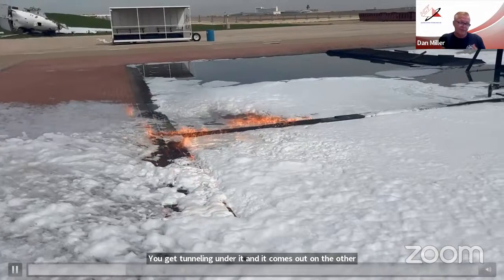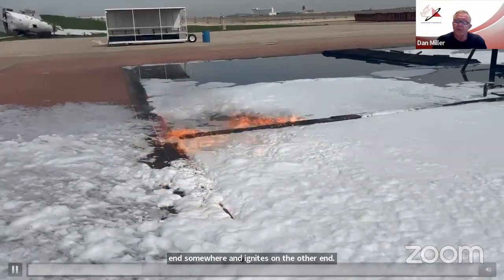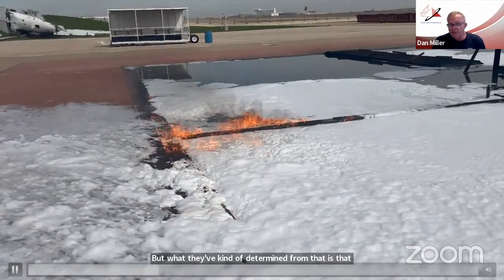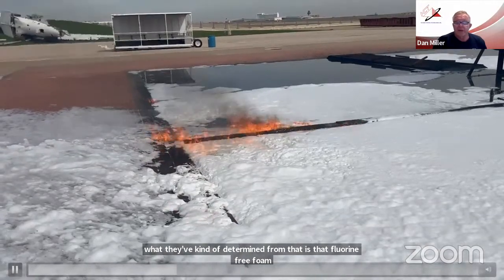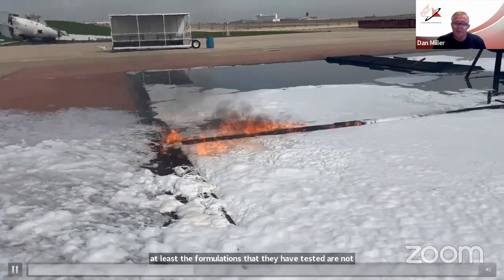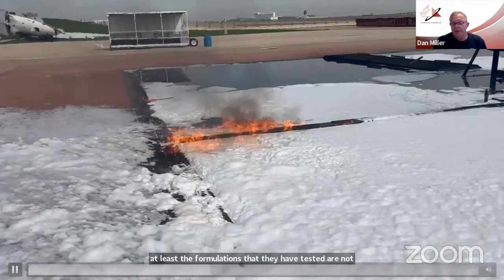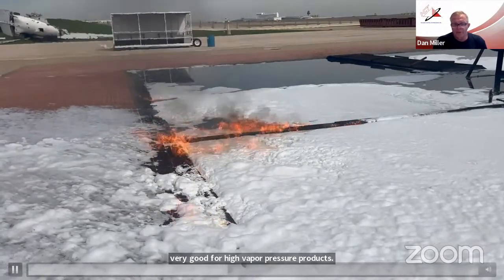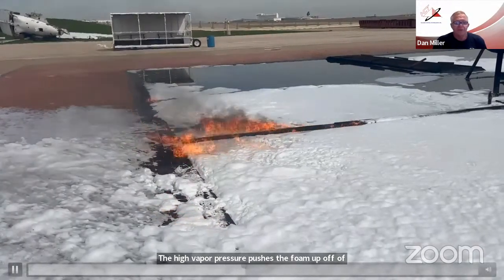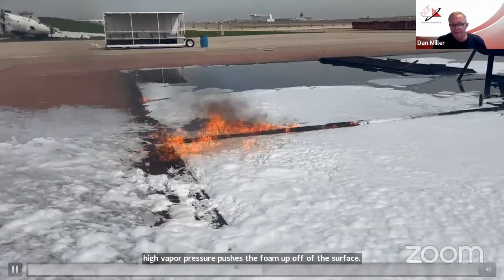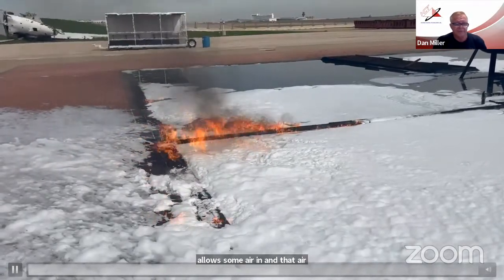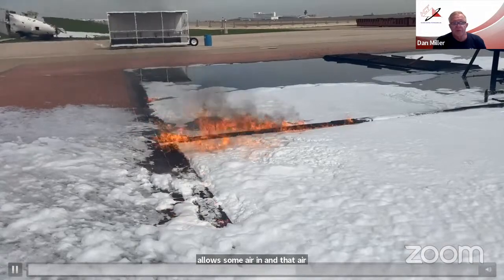What they've determined is that fluorine-free foam, at least the formulations they've tested, isn't very good for high vapor pressure products. The high vapor pressure pushes the foam up off the surface, allows air in, and that infiltration under the foam blanket causes the fire to grow and spread.